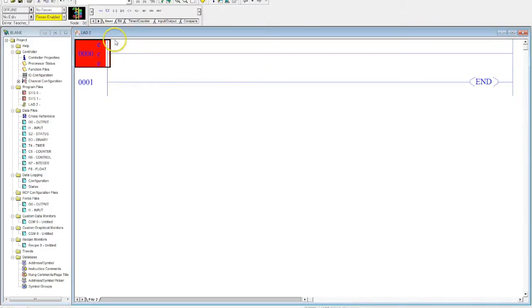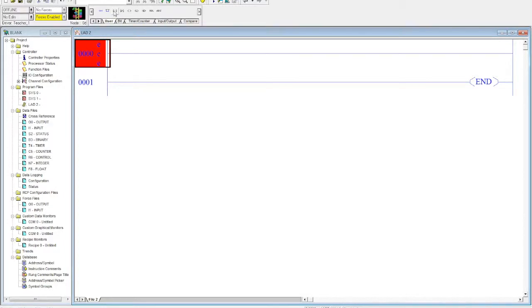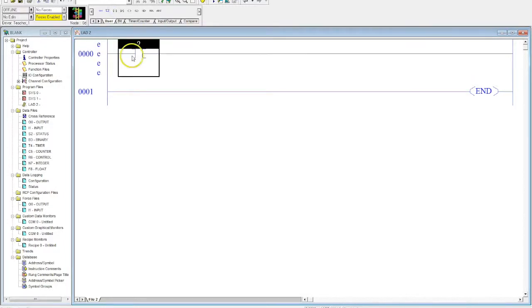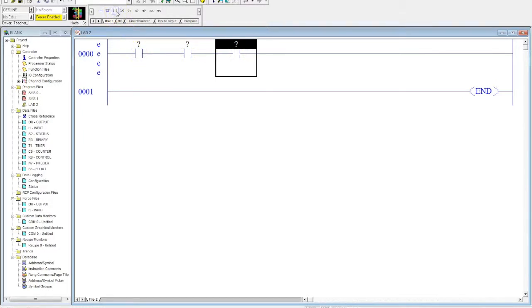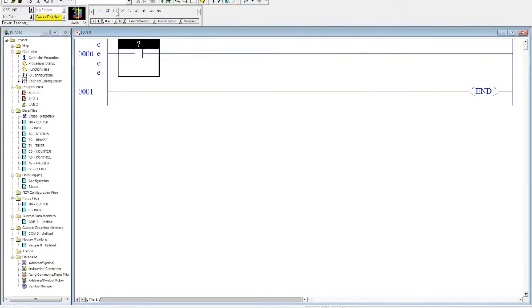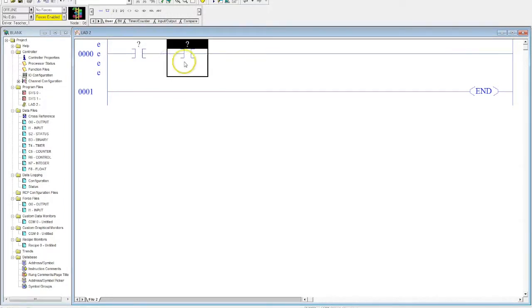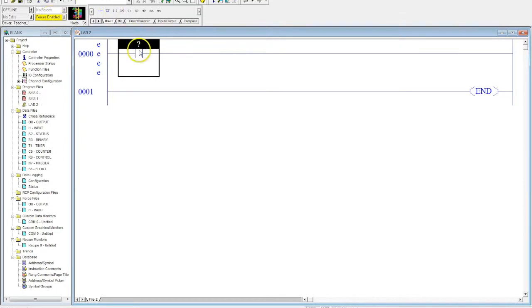So I click here. There are two ways to put an input in here. We're going to use the examine if closed instruction. I'm going to click here and it places it right where I need it to be. The other way I can actually do this is I can click and drag. What you'll notice on some programs in RSLogix 500, especially on older computers, sometimes you click this and it doesn't appear. Then you click twice and then you get two. So what I like to do is just simply drag if I'm unsure. But if I'm on a newer computer, I can just click and make it appear.